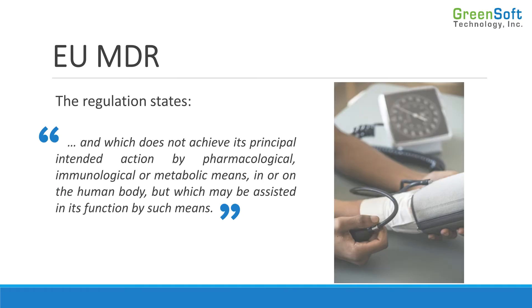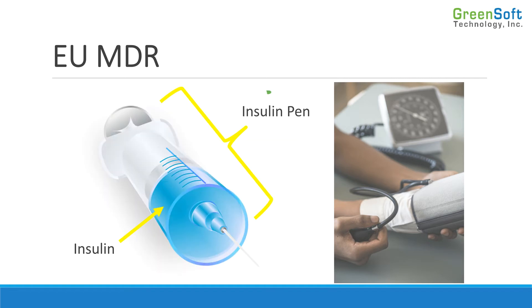However, it does mention that in addition to that, if the product uses pharmacological, metabolic, or other means like this — where it's actually a pharmaceutical — then it's no longer a medical device, but it may be assisted by such means. So in other words, a product that dispenses insulin is a medical device, but the insulin itself is not a medical device.